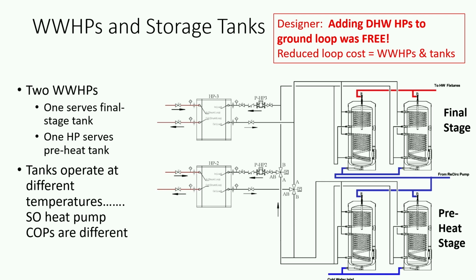And what made this system work pretty well is, in a multifamily building, you always have a recirculation return, and the question is, where should that return come? The water's coming back at 110 degrees or something like that. Should you put it back into the beginning tank, or should you put it back in the middle? These sets of tanks are in series, and we put it into the intake on the final stage tanks, the upper, and so that left the preheat tank to be a lot colder.